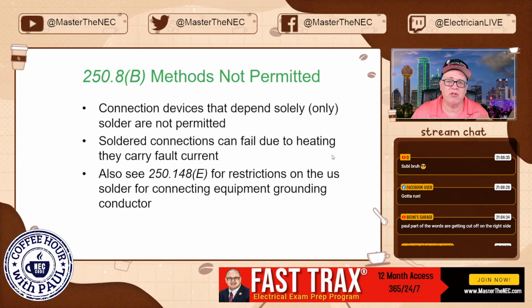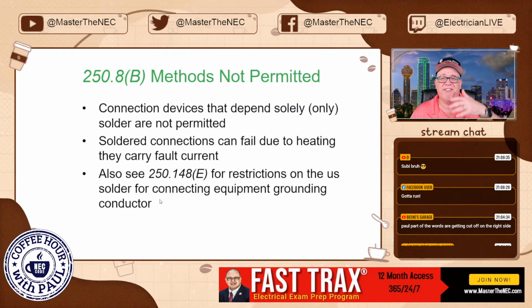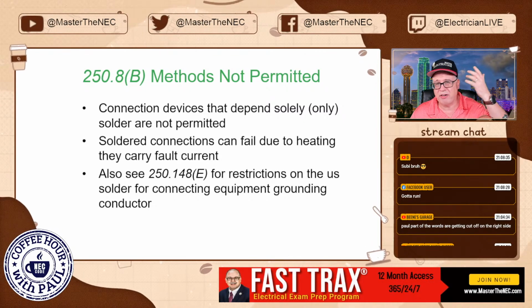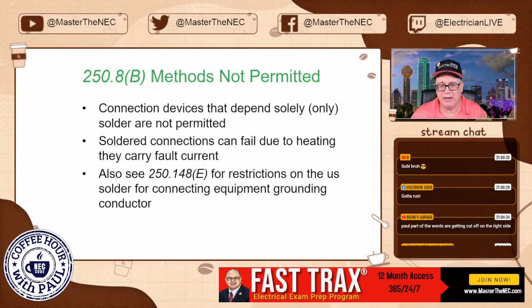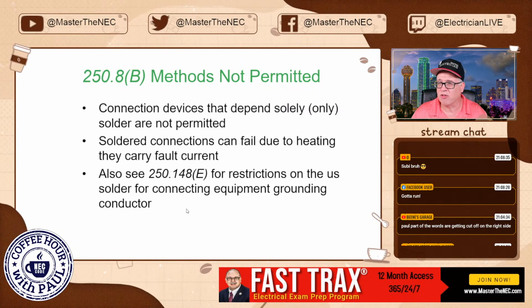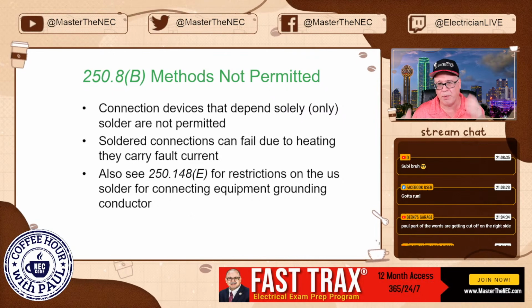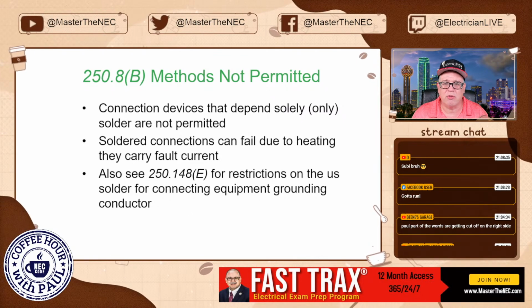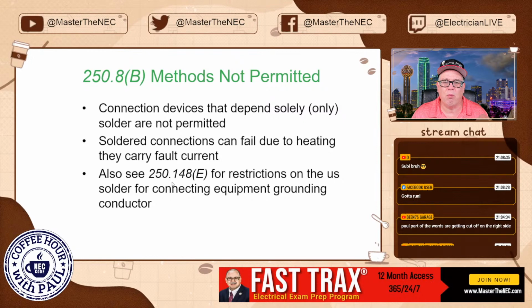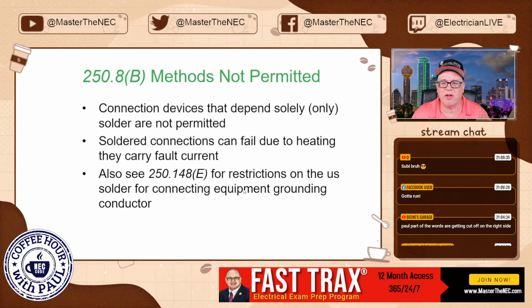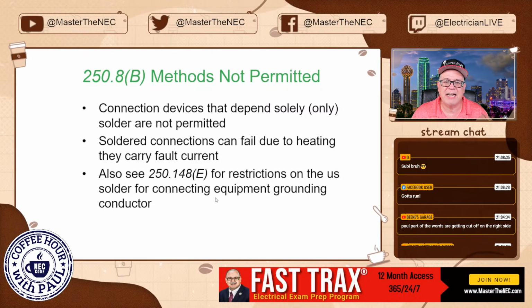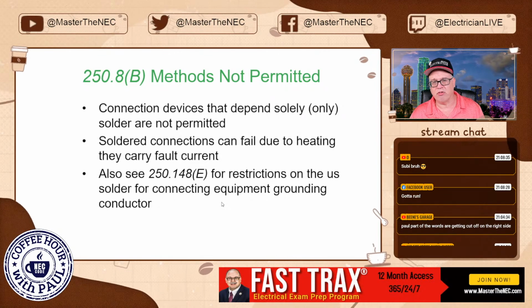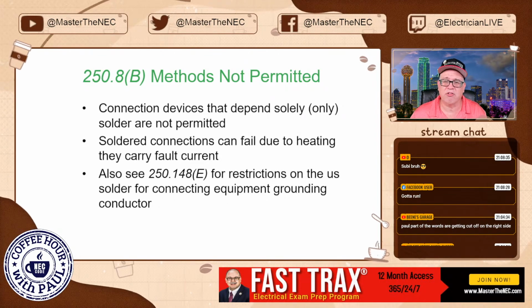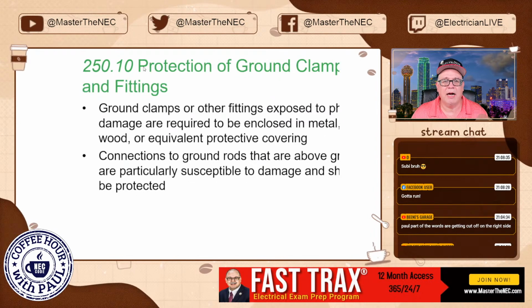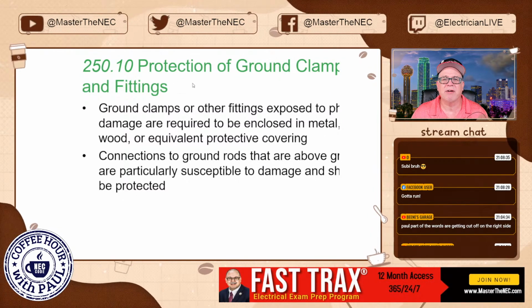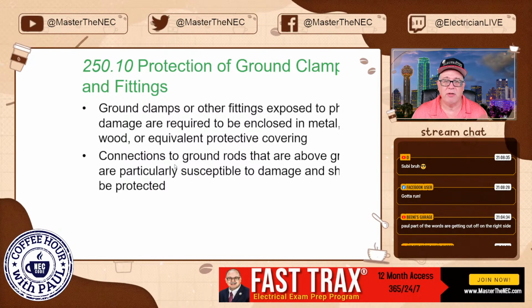Solder conductors can fail due to heating as they carry current. Obviously, could get very high amount of current, can cause a termination to fail or a connection to fail, okay? Talking thousands of amps for a split second could cause a connection to blow apart if it's relying totally on solder. Also see 250.148(E) for restrictions of the use of solder for connecting equipment grounding conductors. Okay, so make sure you go check that out for any restricted limitations that you might have. All right, now 250.10, protection of ground clamps and fittings.